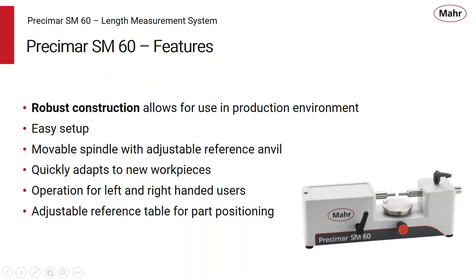There are handles for retraction of the sensitive contact on both sides, and you can even change around the locking mechanism for the adjustable table to make this a left or right-handed device. The adjustable reference table, shown here, acts as a reference stop, just like a stop might be on a snap gauge, for example, that securely holds the part into place between the anvils to provide more repeatability of the part measurement.